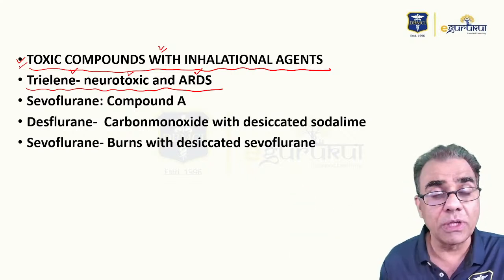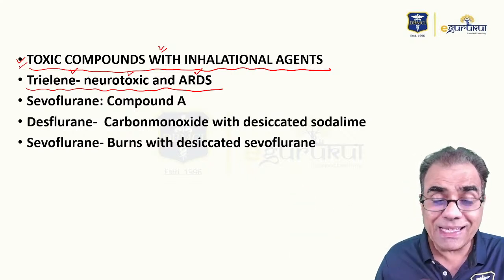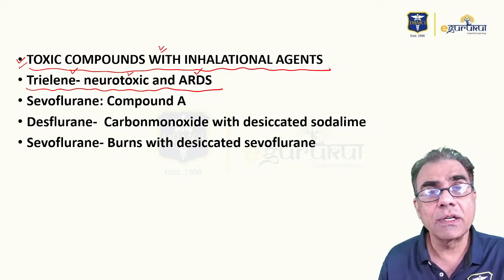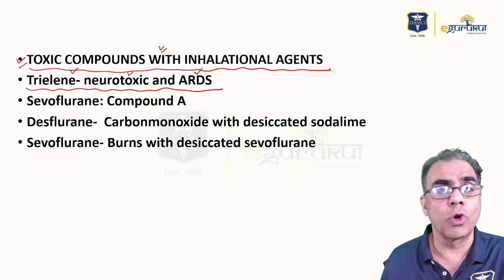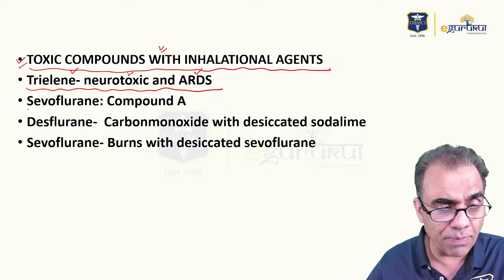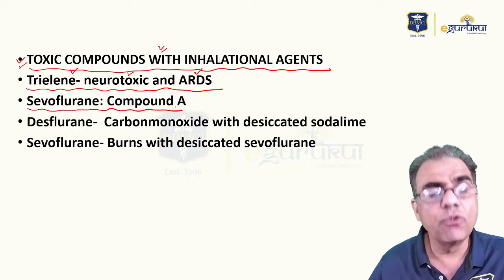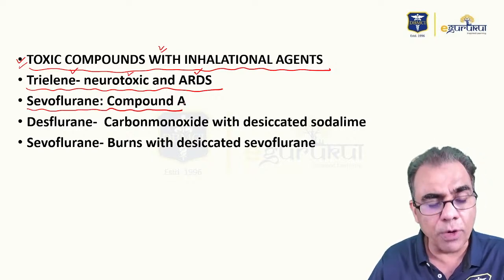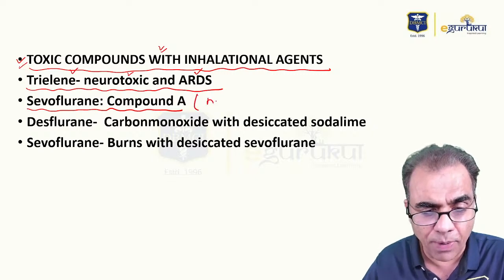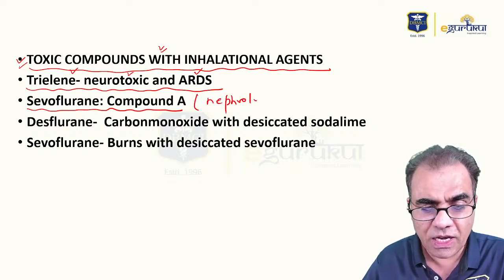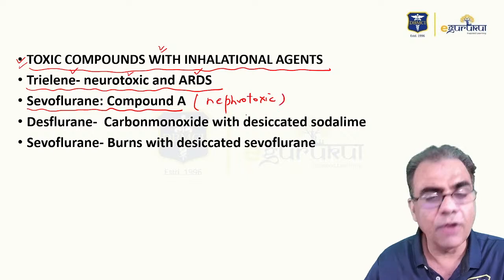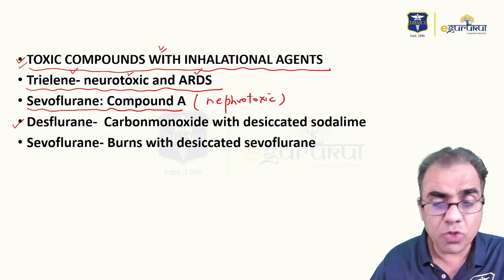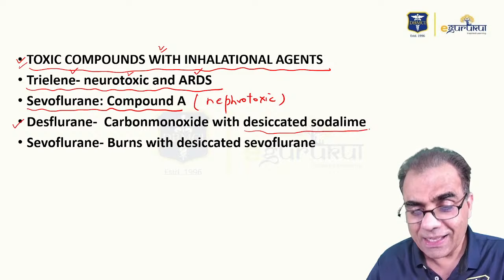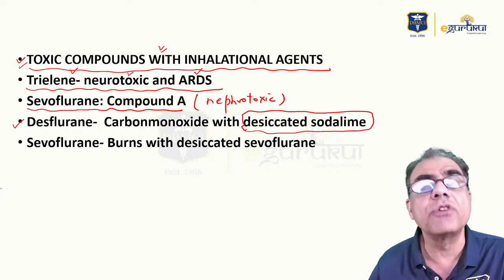But trilene is obsolete. However, the agents which we are using nowadays can also react with soda lime to produce toxic compounds. For example, sevoflurane. Sevoflurane, by reacting with soda lime, produces a toxic compound called compound A, which is nephrotoxic.